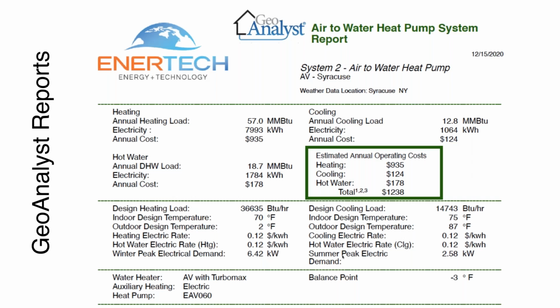This is the report from GeoAnalyst. It gives you the operating costs I mentioned, but also it echoes your design input, heat loss, heat gain, design temperatures, kilowatt hour costs, those kind of things. And then gives you the balance point. In this particular simulation, the balance point is -3 Fahrenheit outside air temperature. So the unit can actually carry the load all the way down to -3. At that point, it either needs the electric immersion heater to come on, or we turn off the compressor and we bring on the boiler. Okay, next slide.